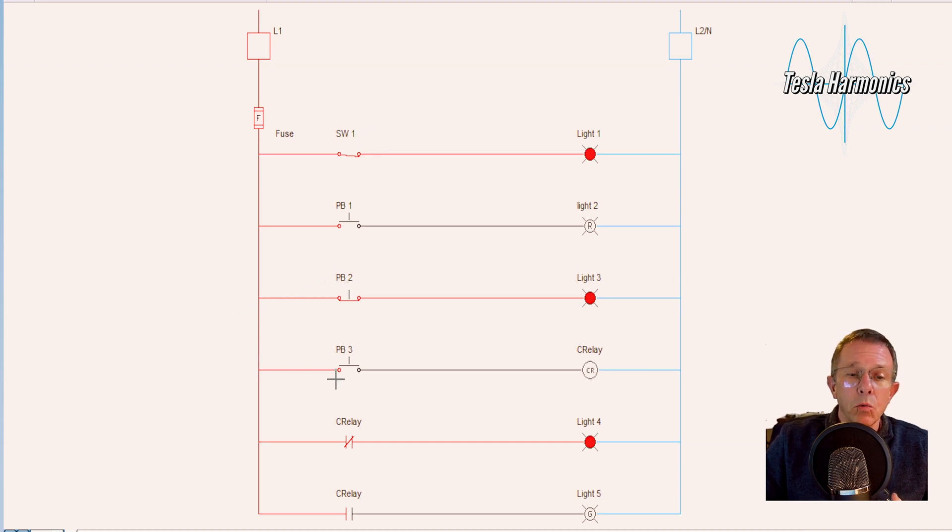Coming down one more rung, I just put in a normally open push button to control our control relay. When we energize the coil on it, it will open this normally closed contact and turn off this red light. At the same time, it will close this normally open contact and turn on this green light.